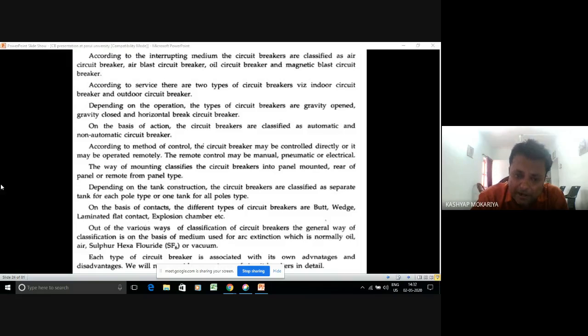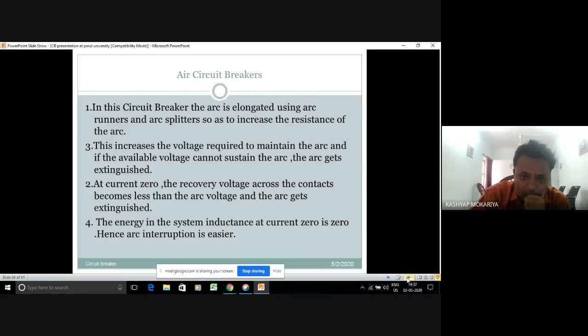The assembly was repaired, and again the pole closing mechanism was observed. After 3 hours of work, it was kept back into service. So this is the air circuit breaker. The diploma engineer as a DET or the degree engineer as a GET has to face this breaker very early in their career, because it is used for 415-volt low tension motors from 90 kilowatt to 160 kilowatt rating in industry. In this circuit breaker, the arc is elongated using the arc runners and arc splitters.